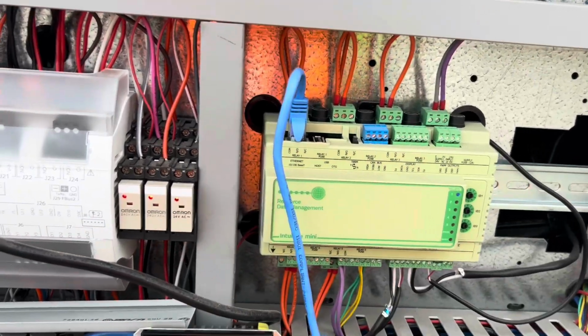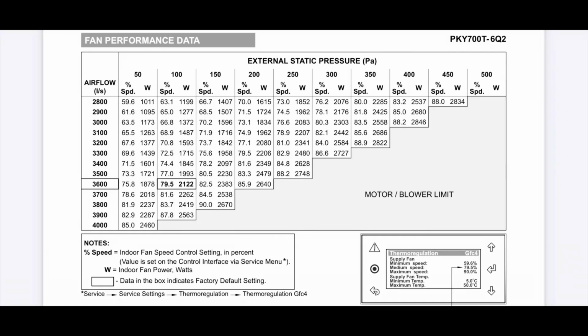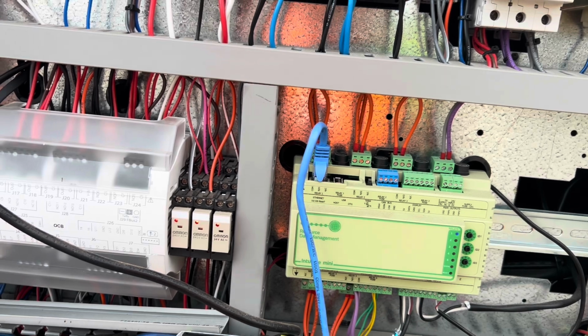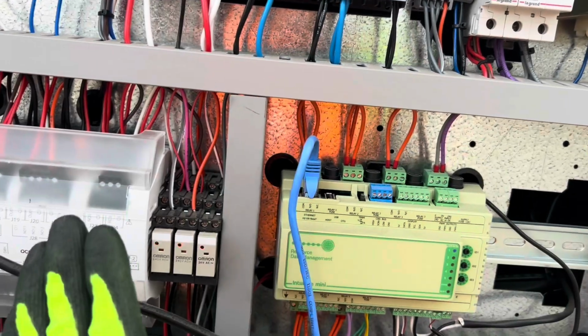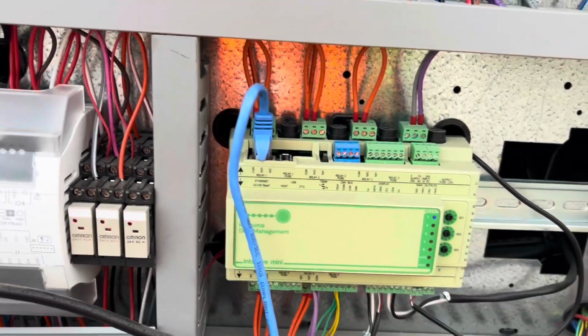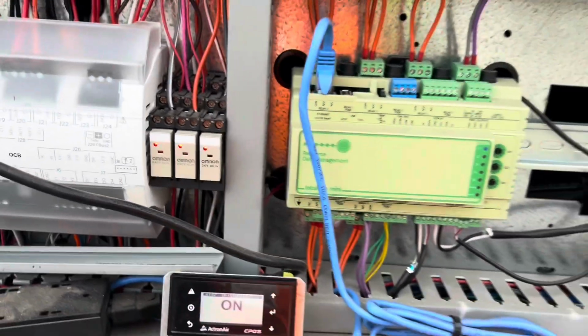So I went and had a look at the commissioning manual - I'll throw up a screen grab - but this one comes preset to, off the top of my head I can't remember, I think it's like 80% potentially for 100 pascals of static. So it's already operating lower than what it should.